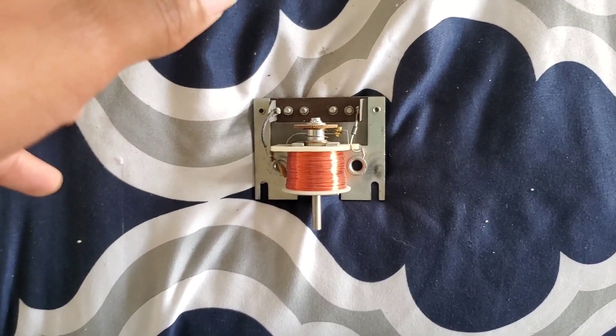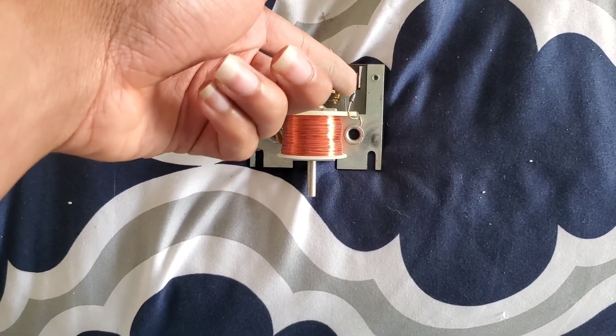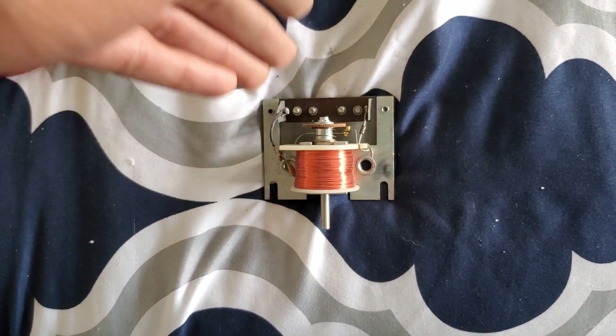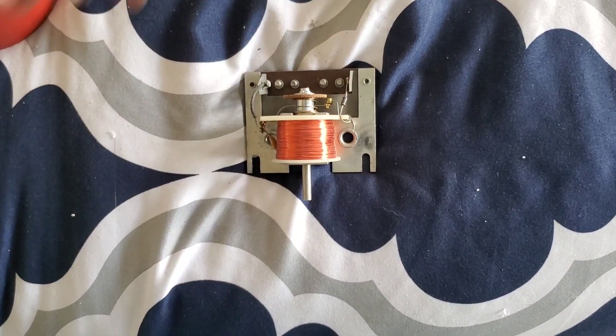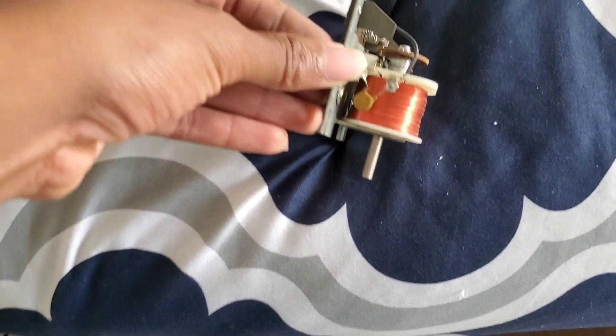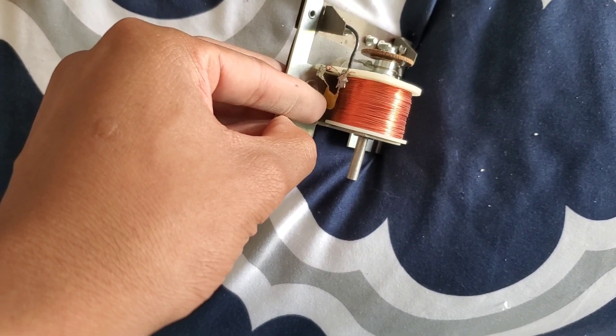Right here you have a diode, which makes it polarized — meaning you can only hook it up one way; current doesn't flow the other direction. That's also how devices are supervised, because panels are checking for that diode, and if they don't find it they throw a fault.